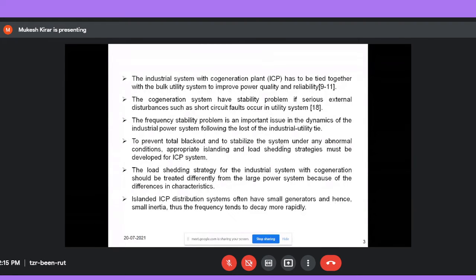Whenever there is an abnormal operating condition in the utility grid, the industrial plant has to separate from it. If we do not separate the industrial plant from the grid, the plant generation and load will collapse. If there is a fault in the utility grid and we do not separate the industrial generation and load from the grid, the fault will collapse the industrial plant also. There will be instability in the industrial system too, because the industrial plant has its own generation and load. If they are separated from the utility grid, they will operate satisfactorily, with less or more load and generation. So they have to separate from the grid.